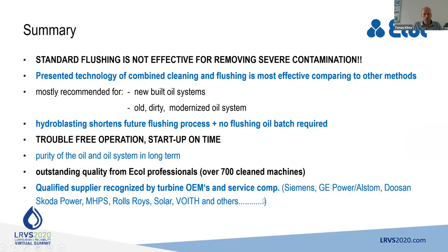My summary, very short. I would like to stress the standard flushing is not effective for removing severe contamination. As you see at the beginning, severely contaminated pipes, you will not flush even with an external skid. The present technology of combined cleaning and flushing is most effective compared to other methods. Recommended for new build as well as overhauled and modernized systems. Hydroblasting shortens the future flushing process, which is very short if you cleaned it properly.